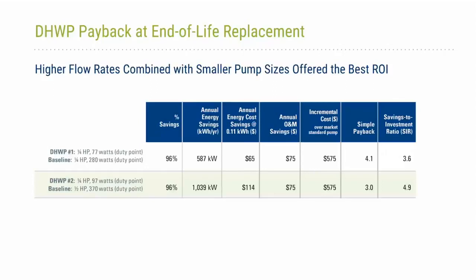One thing to note, though, is that the annual O&M savings was $75 a year, and the on-site staff were estimating that those savings come from not having to grease the bearings or replace the pump seals. So the O&M savings for these small pumps are very significant, as much or more than the energy savings. And then we looked at the economics in terms of an end-of-life replacement. So, assuming that you have a domestic hot water pump that has failed and we're putting in a new one, these are roughly $575 more expensive than the market standard pump. So in those cases, the simple payback you can see is 3 to 4 years. So very attractive payback for both applications there.